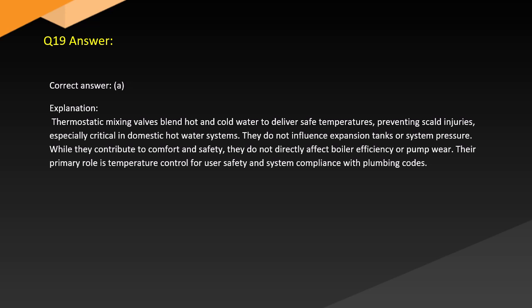Answer. Correct answer: A. Explanation. Thermostatic mixing valves blend hot and cold water to deliver safe temperatures, preventing scald injuries, especially critical in domestic hot water systems. They do not influence expansion tanks or system pressure. While they contribute to comfort and safety, they do not directly affect boiler efficiency or pump wear. Their primary role is temperature control for user safety and system compliance with plumbing codes.